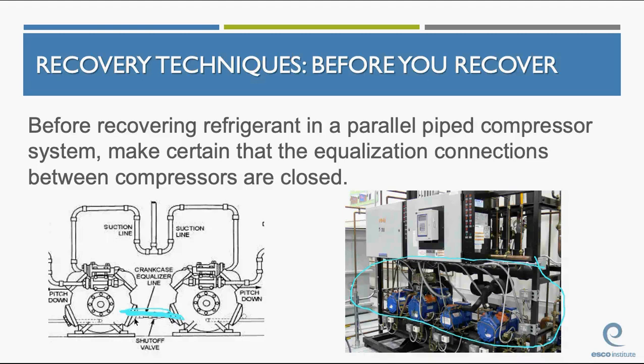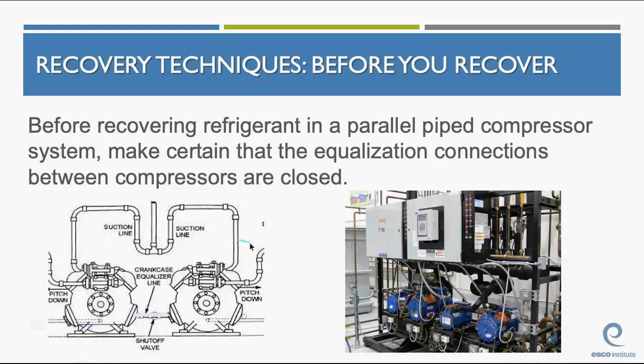Okay, what that does, it allows oil and pressures to equalize between the two compressors. Okay, they're piped in parallel. So every compressor running adds to the total output of the system. But in order to equalize, and to make sure that we have oil flow and everything like that, there's an equalizer valve between the crankcases of these compressors. Okay, it's very important when you're recovering from one compressor. Let's say this compressor on the right is dead.